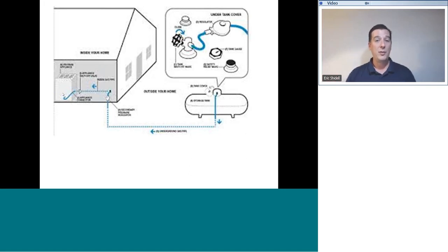In that case, there will be a gas regulator at the appliance to step it down to the 7 inches water column that the appliance needs. Most all fuel-burning appliances that you'll find in a home or a building will operate at that 7 inches water column pressure rating. And we'll talk a little bit more about that later.